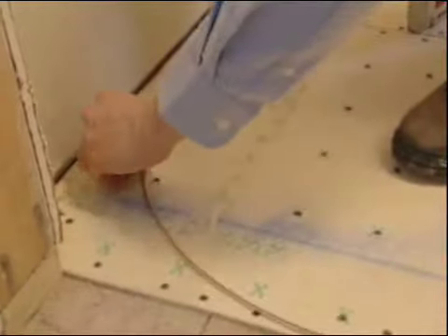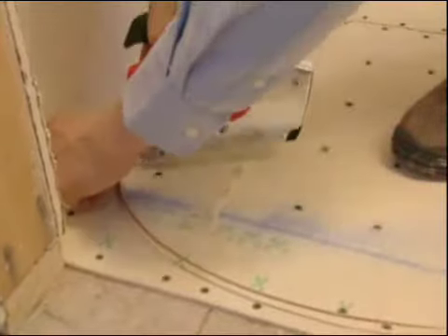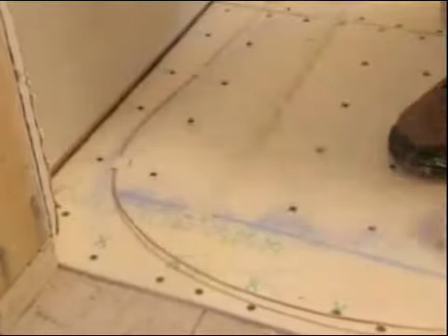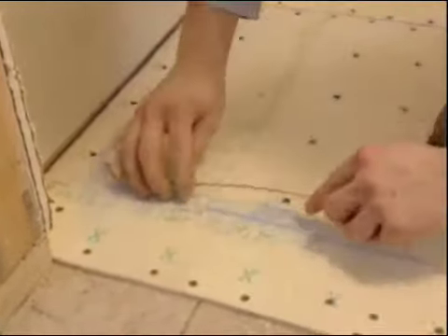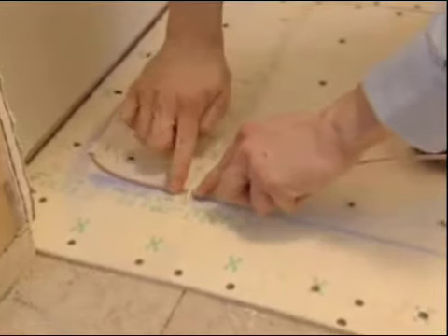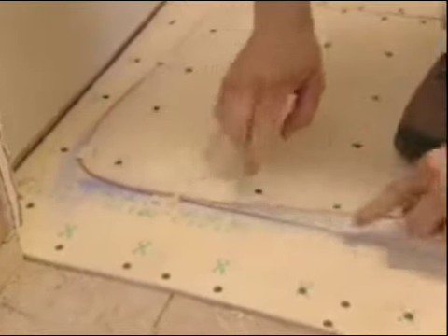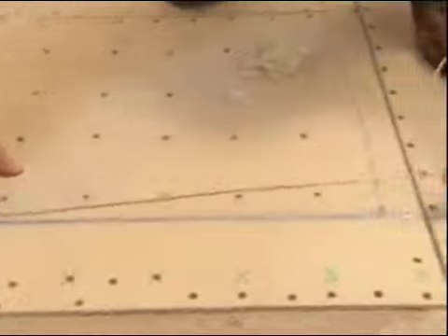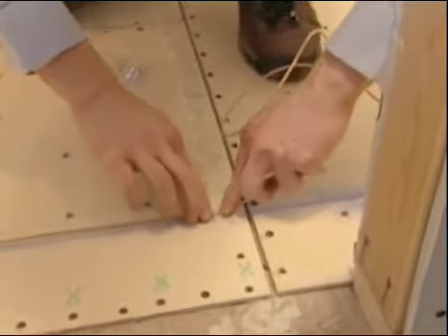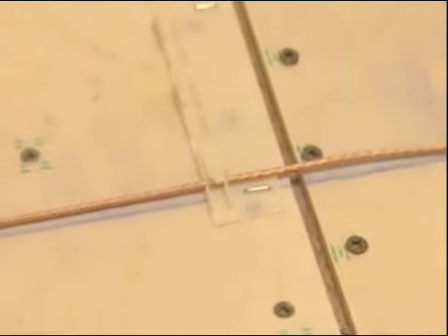Staple the clips into position, being careful not to penetrate the cable. When routing heating cable to the beginning of the strapping, use clips to attach heating cable to the subfloor. Close the first 1 or 2 hinged clips on the strapping in order to hold the cable securely before proceeding to the next strapping run. Subsequent clips should be left open until cable placement is completed.